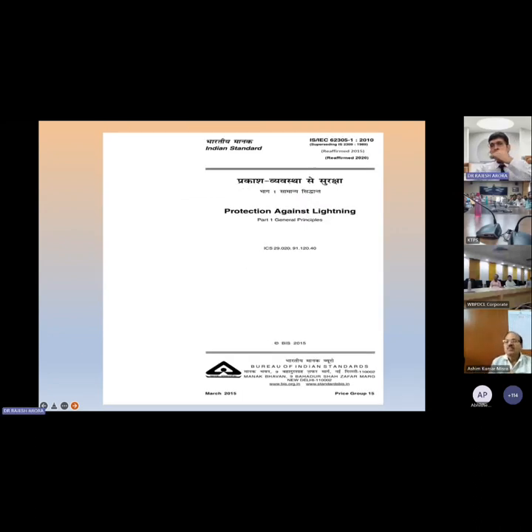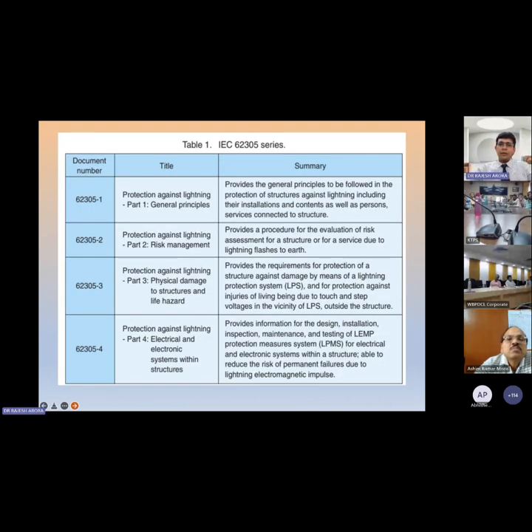When you are in a building, you are in an office, you are in multi-story buildings, another IS, IEC 62305, that is related to protection against lightning, must be followed. That should be part of your library. It has four parts. 62305 part one, protection against lightning, general principle. Part two talks about the risk management. Part three talks about the physical damage to structures and life hazard. Part four talks about electrical electronic system within structures.